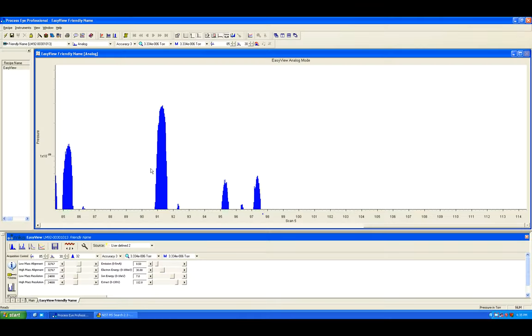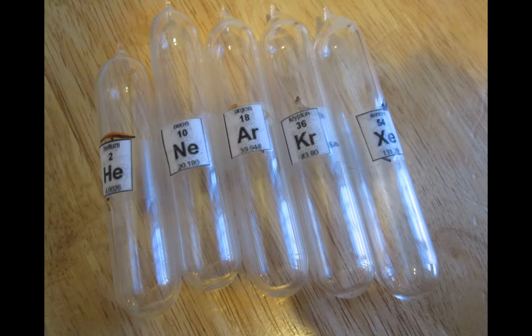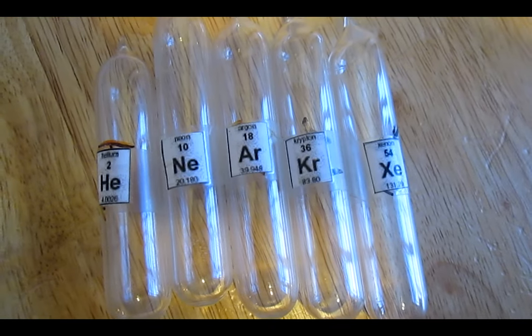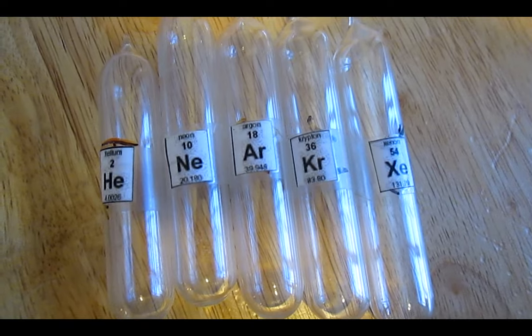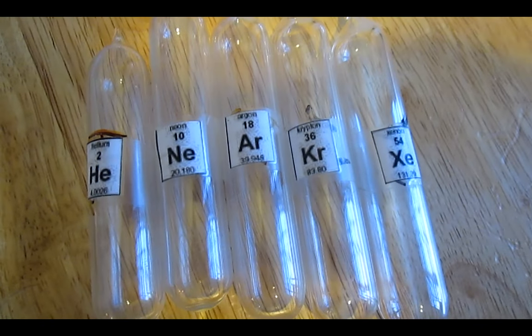And this is how some oddities like neon oxide plus, argon chloride plus, or single methyl radicals can be observed. The noble gases travel alone, solo, so there's nothing to split, but they can do something else.